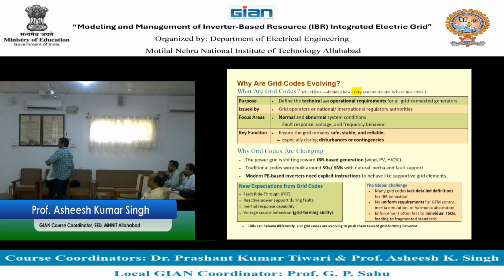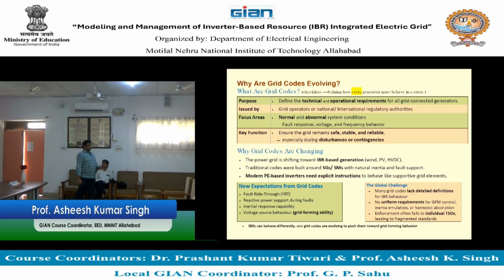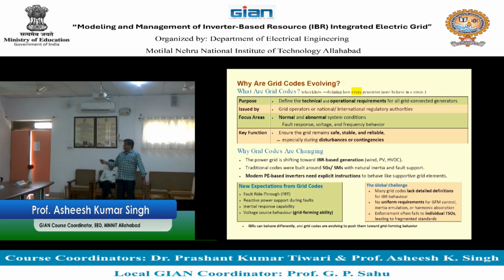So the purpose is to define the technical and operational requirements for all grid-connected generators. Grid codes are issued by grid operators, national or international regulatory authorities. The focus area is normal as well as abnormal operation, both - abnormal system conditions, and they measure fault response, voltage and frequency behavior.